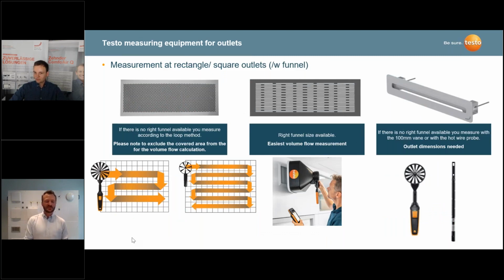As mentioned before, if you have a fitting funnel we always recommend it because it's easier to calculate the airflow. For bigger outlets, mostly used in non-residential buildings for more people, we suggest the loop method: you go around the outlet like this, and then calculate the volume flow afterwards, or sometimes the device offers automatic calculation with the dimensions entered in the instrument.